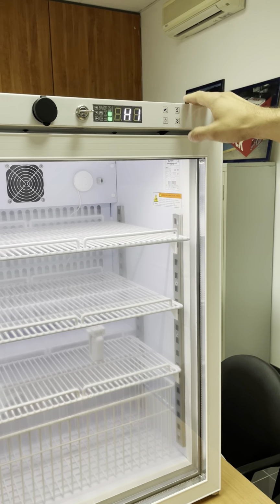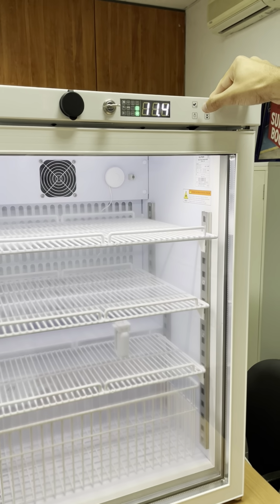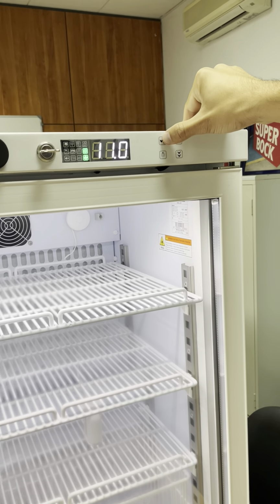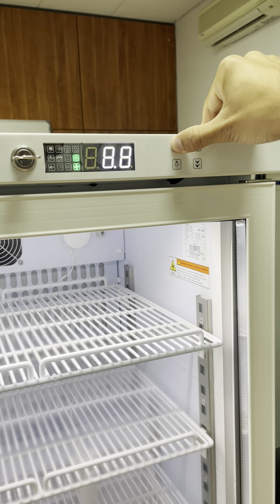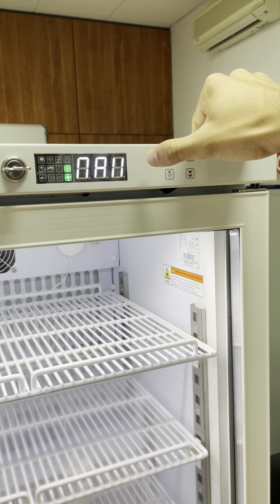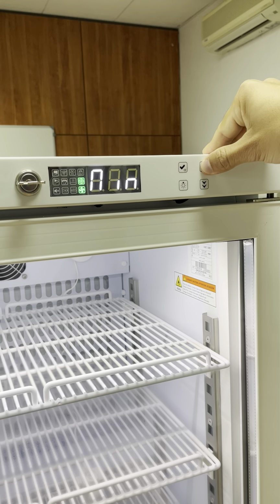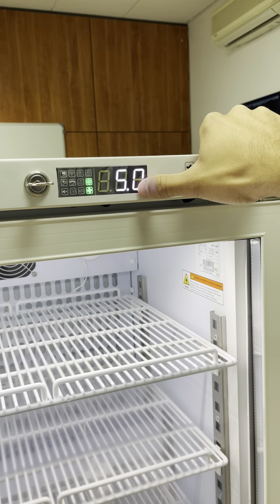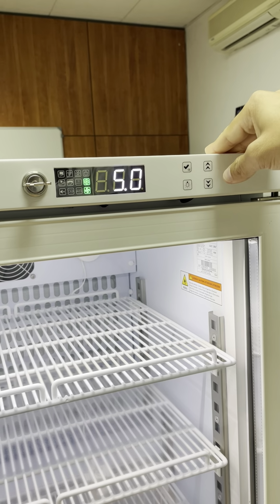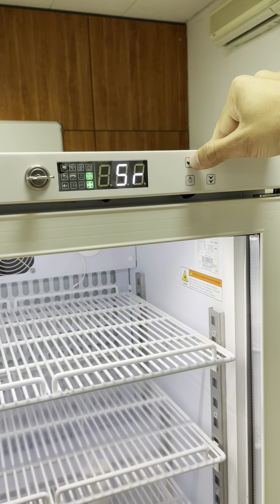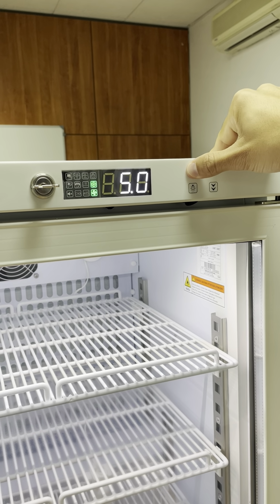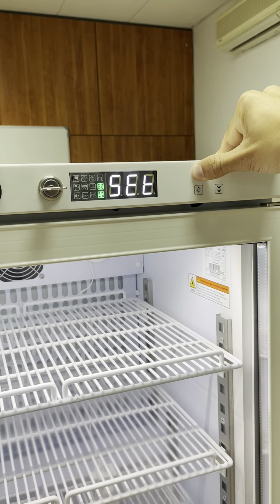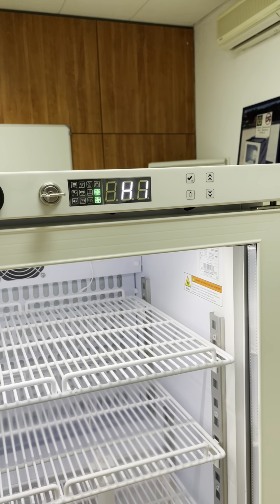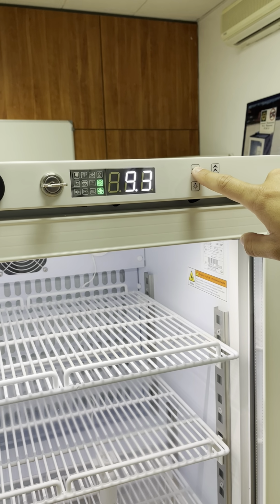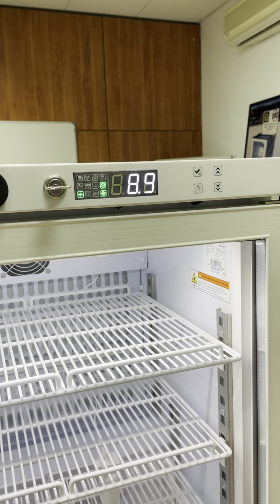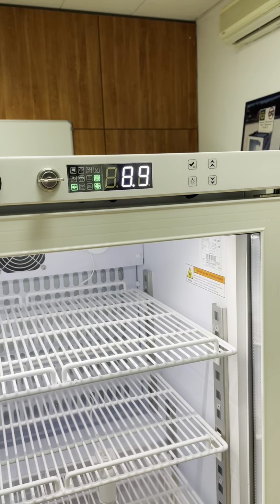In the meantime, I will show you how you can see the set point of the equipment. If you press the set button for some time, you enter the parameters. Here is max. I will show you what this is in a minute. Min, clear, and set. If you enter set, you see the set point defined for this equipment, that in this case is 5 degrees. The others I will explain in a minute. It's going out of the parameters. Of course, you can silence the alarm anytime if you click this button. We just silence the alarm. So we need to wait until it goes below 8 degrees again.